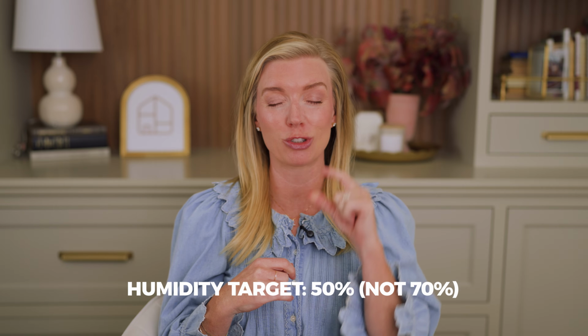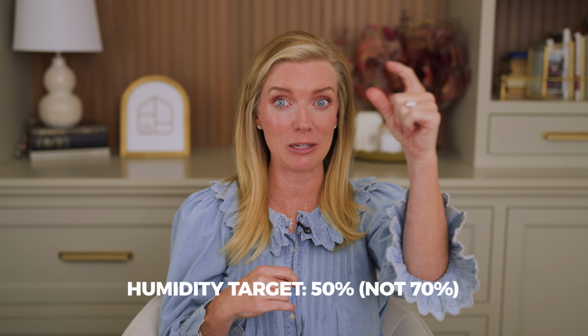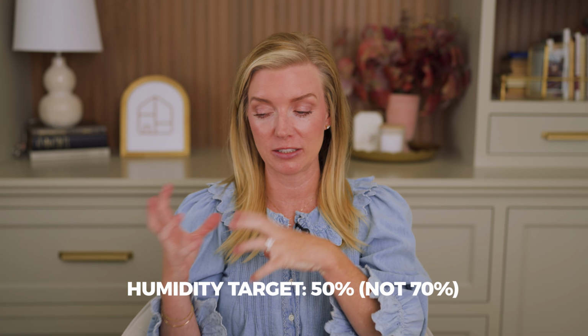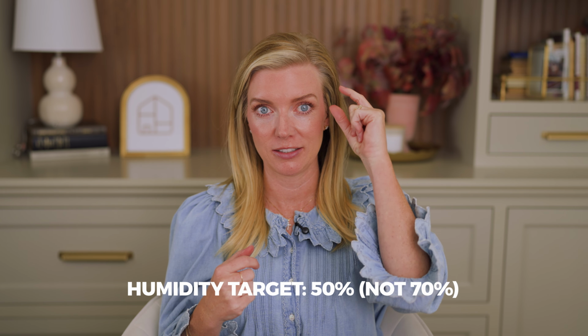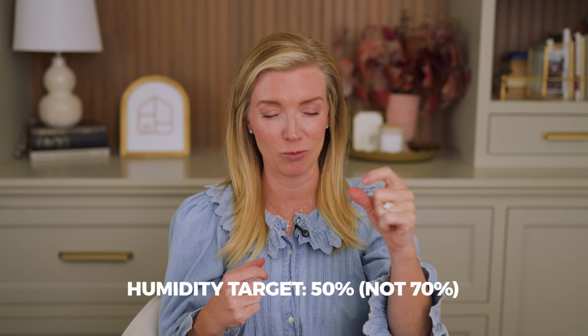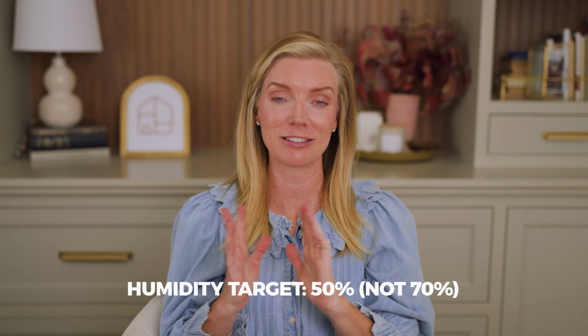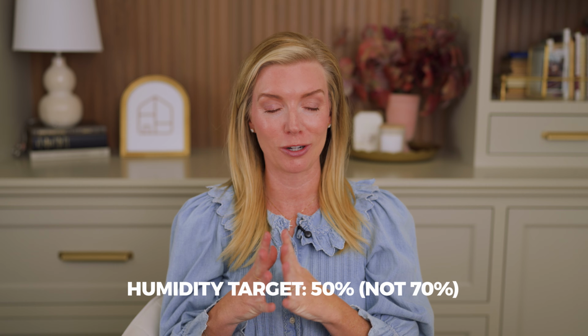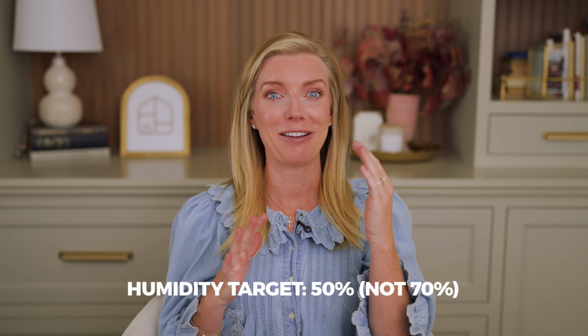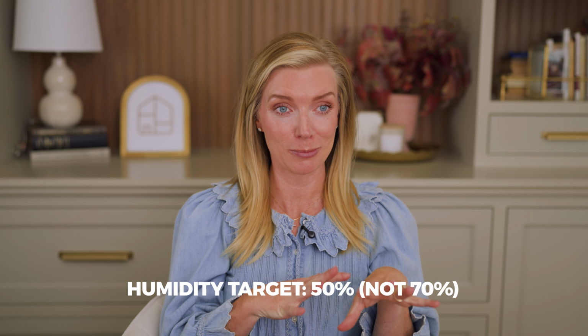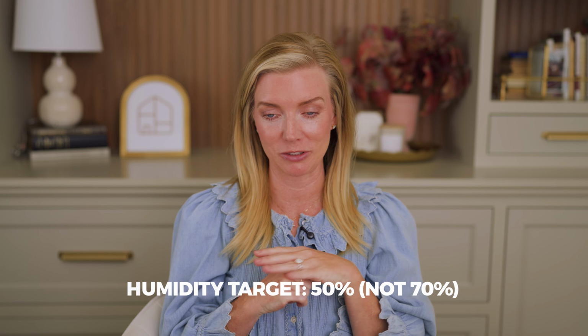I still see a ton of loopholes and not properly calculated equipment sizing. And the biggest thing I see is indoor humidity set points extremely high, like 70%, meaning these calculations are targeting 70% indoor humidity, which in the healthy home space we do not want. It would be much more comfortable and ideal around the 50% mark.